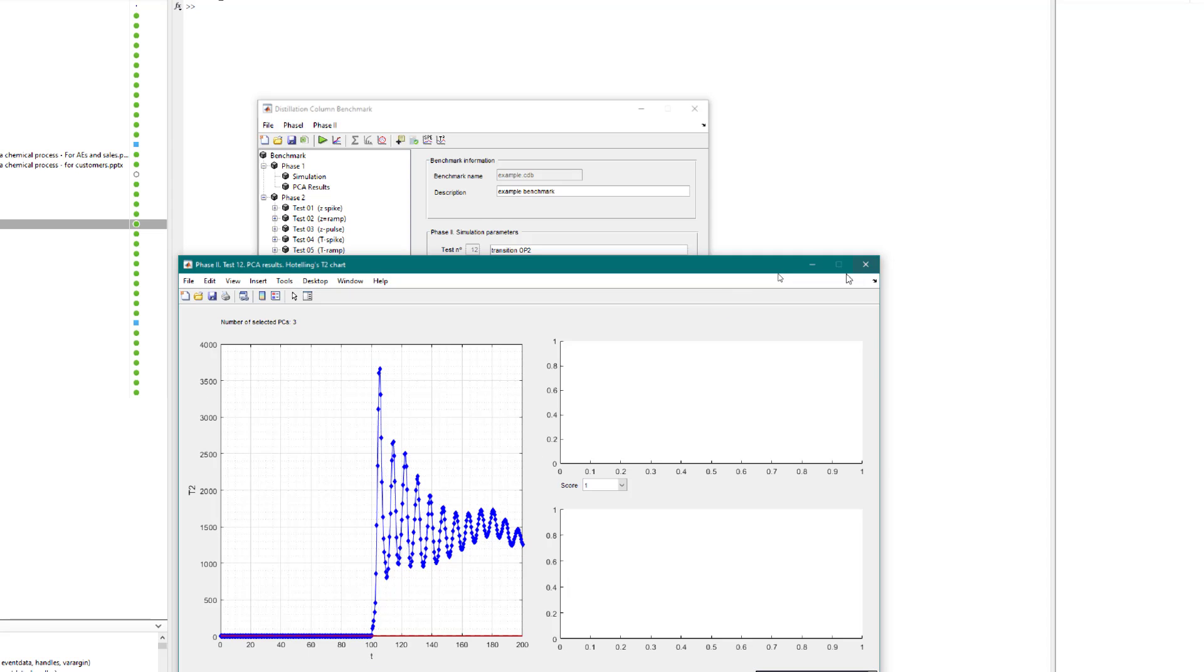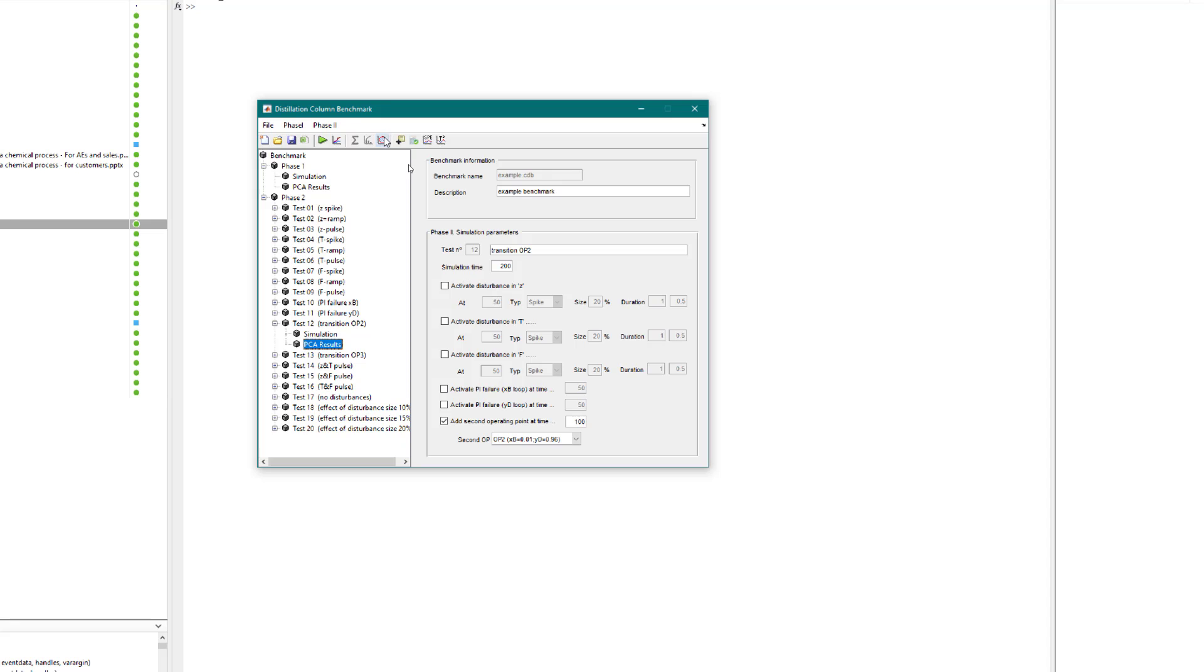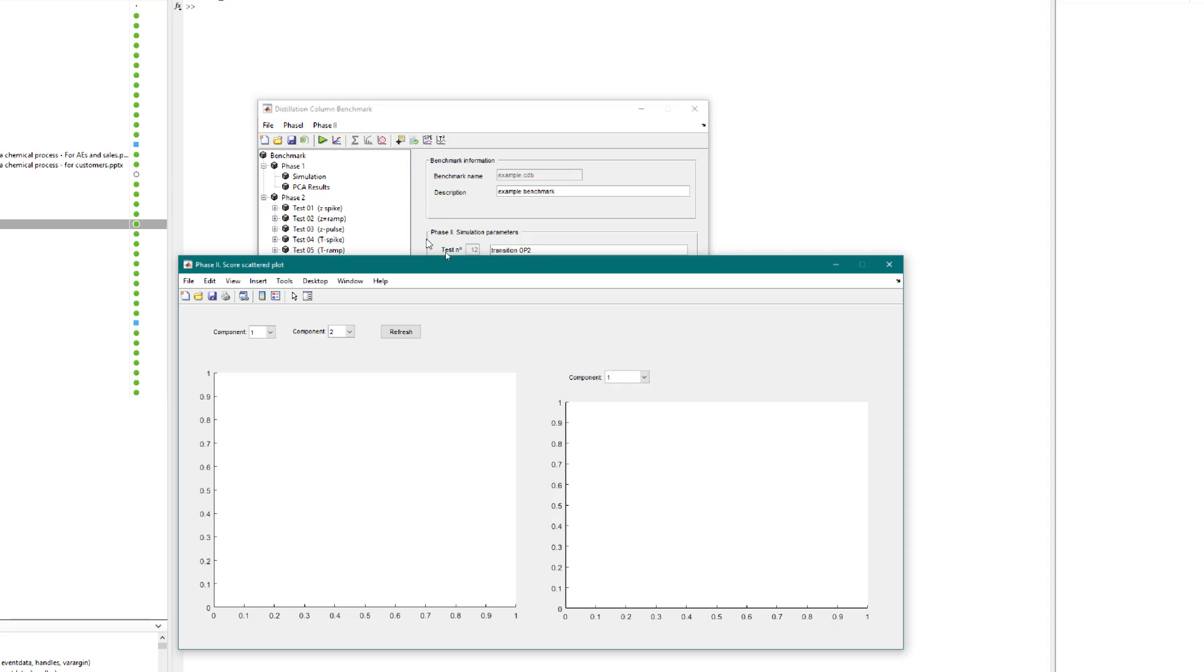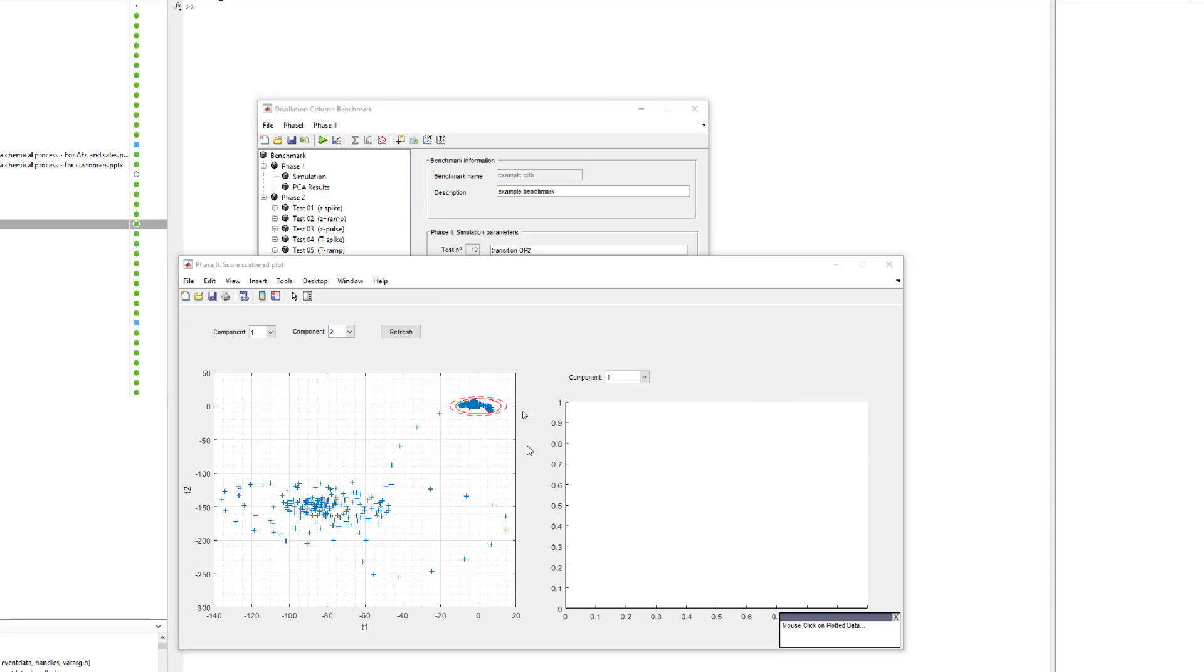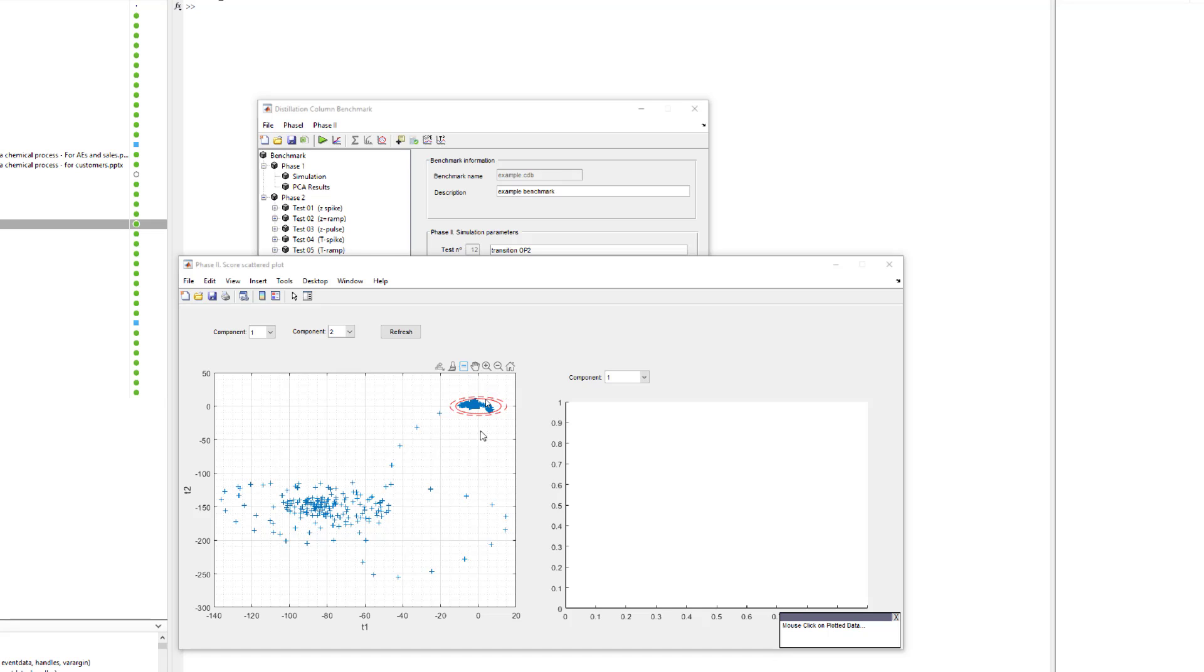The scores plot reveals a lot of additional insights in this case. We see there is a distinct cluster of points at the origin and one over here. Remember that we have trained the steady state PCA model only for one set of conditions, which is the operating point one. We have not trained the PCA model to recognize anything outside of this. Hence, even if it is a stable condition at the operating point two, the model believes that it is a fault and shows it so. In this case, it is clear that just looking at the contribution plots was not helpful. We need to pair it with our knowledge of the process and our domain expertise in order to get at the root cause of the failure.